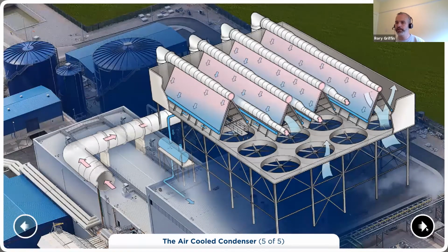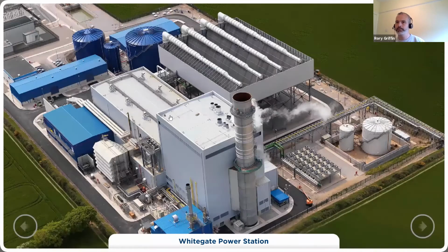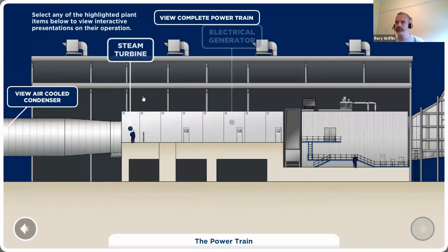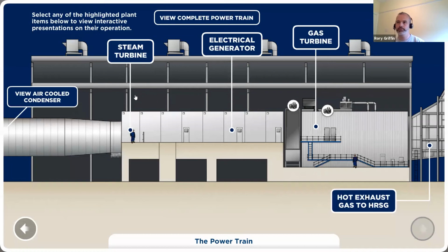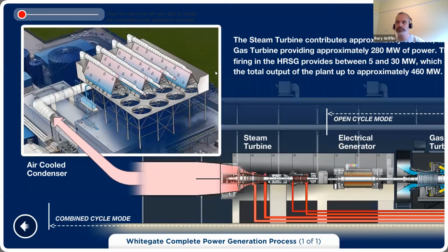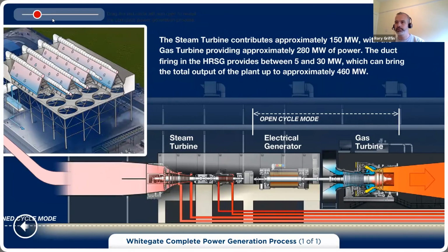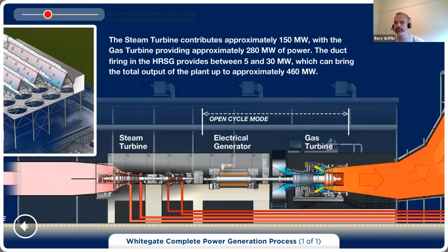So all we've done so far really is talked about rotational power, and we haven't discussed yet electricity. Now, I'll come to electricity generation on the generator in 1 second. I just want to hit this powertrain here just to give you an idea. So this here is the complete powertrain, and just something to bear in mind is there's 8 bearings in the machine. So there's a bearing here inside an exhaust. We have a bearing here just before the load coupling. There's a bearing either side of the generator. There's a flex coupling between the generator and the steam turbine.